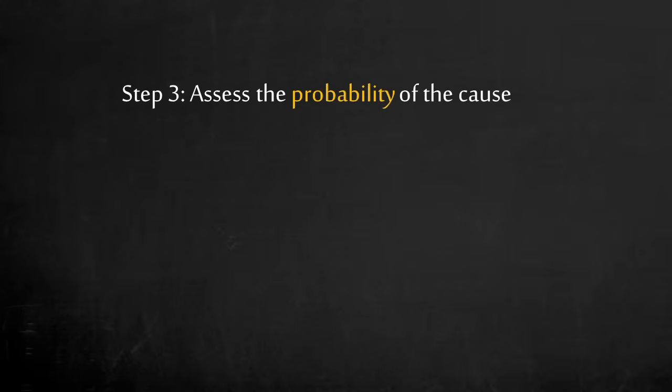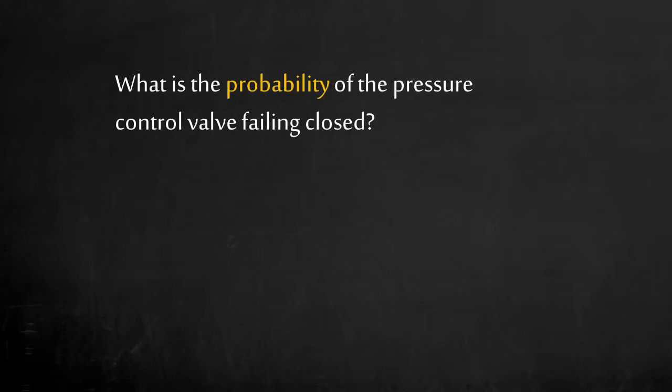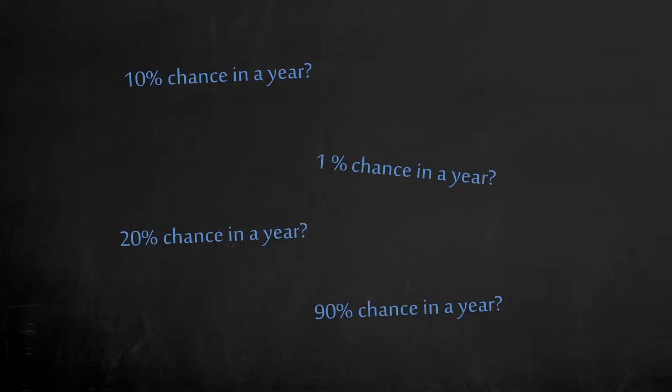Step 3: Let's assess the probability of the pressure control valve failing closed without safeguards. The probability of the pressure control valve failing closed includes all possible root causes, such as logic controller or sensor output error. Based on different operating and engineering experience, there may be different opinions. Is it 10% chance in a year, 1% chance in a year, 20%, or maybe 90% chance in a year? The HAZOP team needs to reach a consensus.